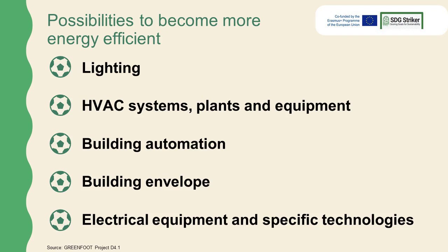Reducing the environmental impact of energy-consuming systems requires two synergistic approaches. First, it is necessary to reduce energy losses and thus the overall energy consumption through implementation of energy efficiency measures, and second, the remaining energy demand can be provided via renewable energy sources. Each case needs to be assessed individually in order to identify the weak points and the most promising optimization potentials. For football facilities, the following relevant areas of improvement should be considered: lighting systems, HVAC (heating, ventilation, air conditioning) systems, building automation or building management systems, the building envelope, and electrical equipment, as well as specific technologies for sports facilities.